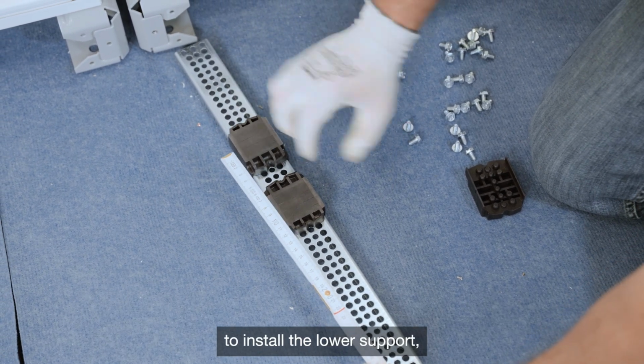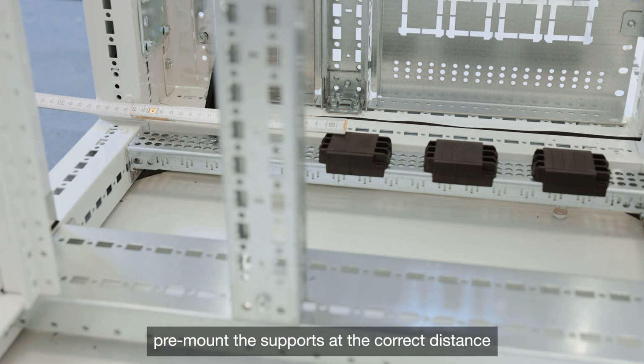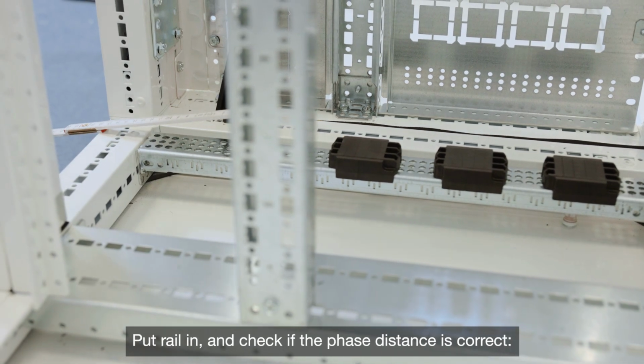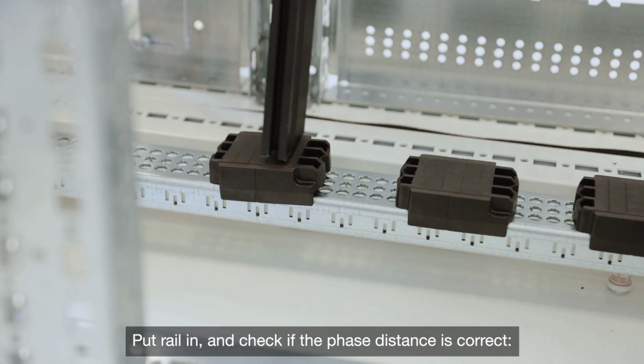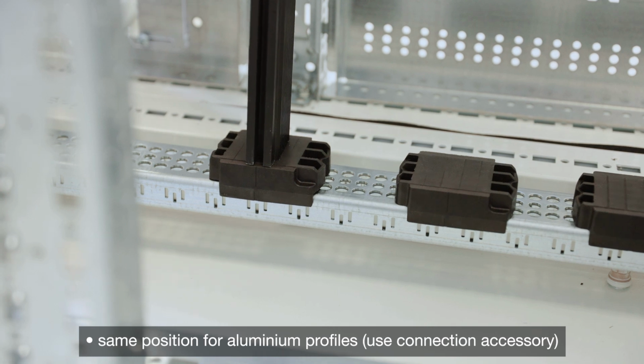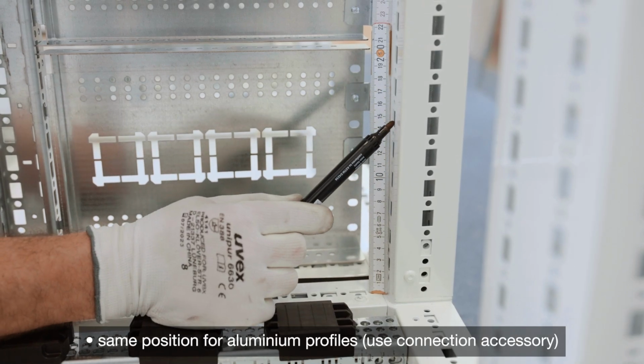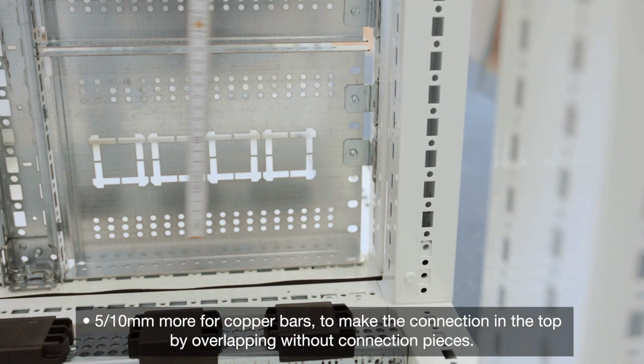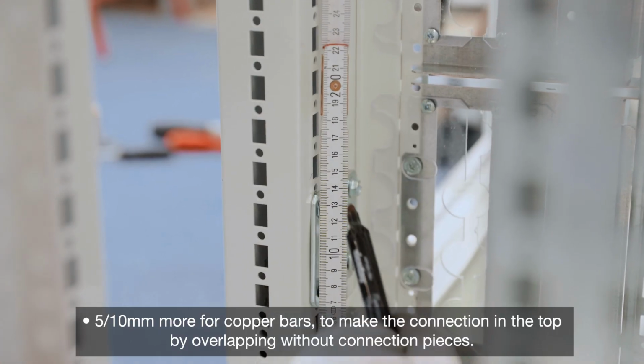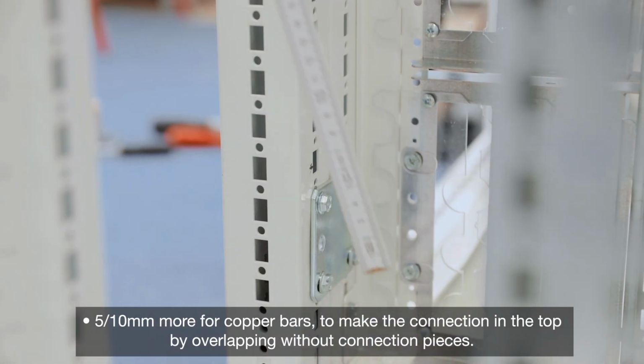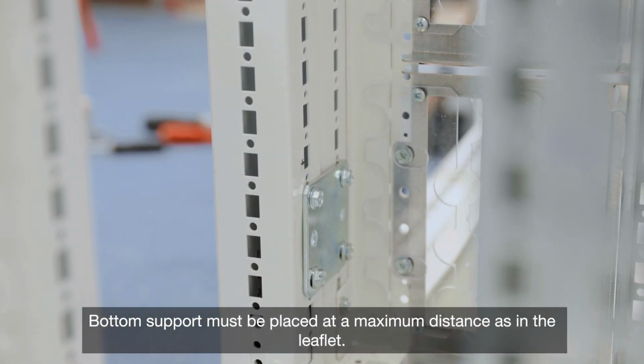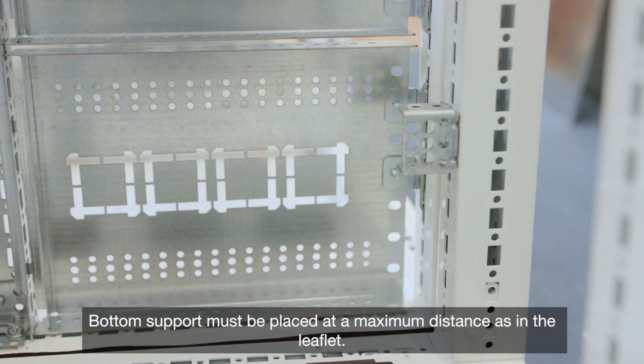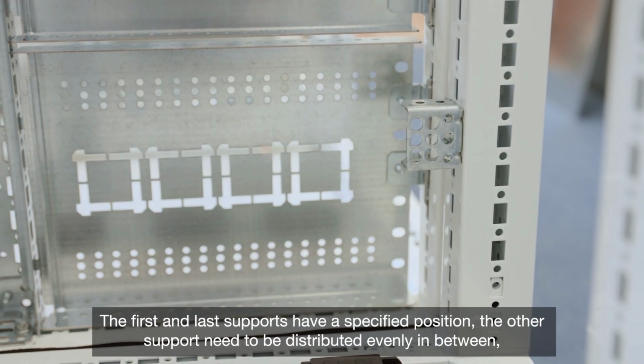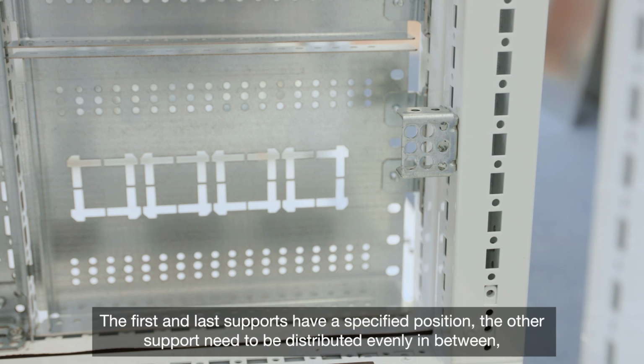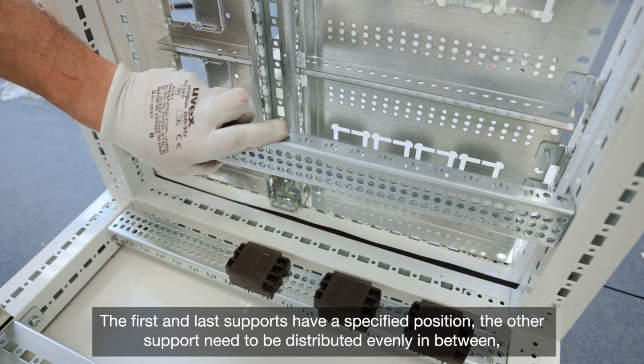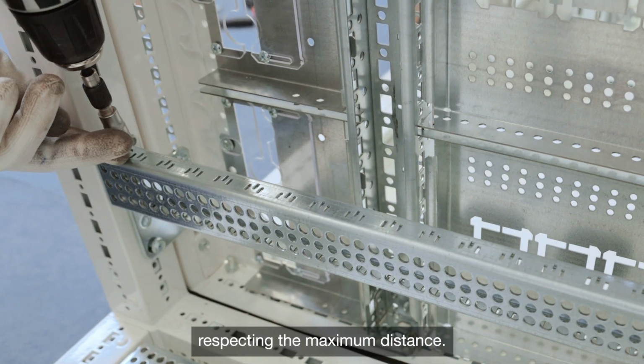To install the lower support, pre-mount the supports at the correct distance. Put the rail in, and check if the phase distance is correct. Same position for aluminium profiles. Use connection accessory, 5/10 mm more for copper bars, to make the connection at the top by overlapping without connection pieces. Bottom support must be placed at a maximum distance as in the leaflet. The first and last supports have a specified position. The other supports need to be distributed evenly in between, respecting the maximum distance.